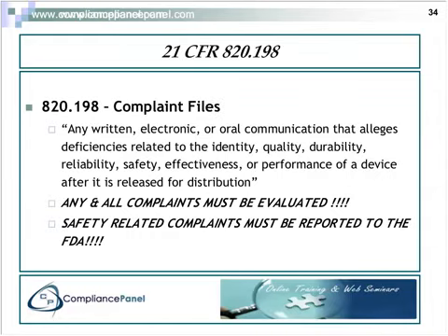Next, we have complaint files. Complaints are usually the main focus of an FDA audit. I know when they've come to my facility, the first thing they ask to see is the person in charge, and then when he has gone through his introductions and given them the escorts, the next thing they want to look at is your customer complaints. And as you can see by this slide, the definition of a complaint carries a very broad range of communications, and any and all employees could be the recipient of a complaint.